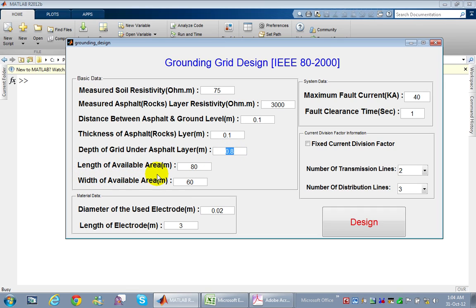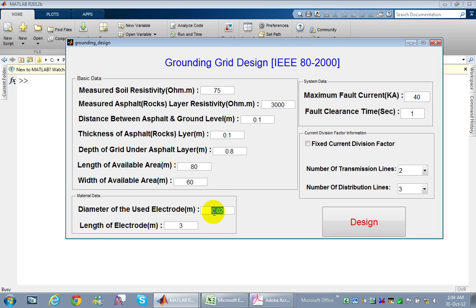The length of the substation area is assumed to be 80 meters and the width 60 meters. Regarding electrode dimensions, per Saudi Electricity Company specifications we use electrodes with a minimum diameter of 0.02 meters and a length of 3 meters.